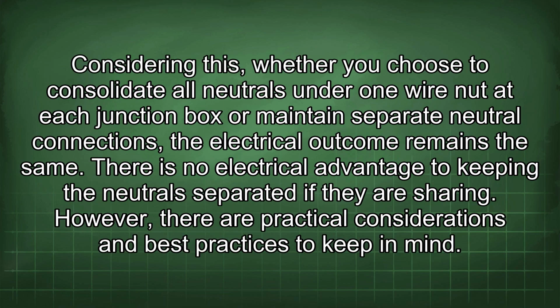Considering this, whether you choose to consolidate all neutrals under one wire nut at each junction box or maintain separate neutral connections, the electrical outcome remains the same. There is no electrical advantage to keeping the neutrals separated if they are sharing. However, there are practical considerations and best practices to keep in mind.